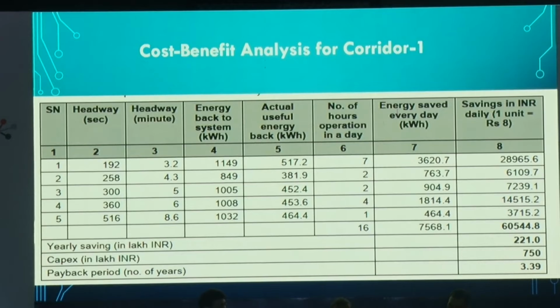We have done a cost benefit analysis for corridor 1 of Kanpur Metro. As per the headway in the DPR, considering 16 hours operation in a day, we could save an energy of around 7,500 units in a day, which translates into 2.2 crores rupees of saving in a year. Considering a cost of transformer 2.5 crores as of now, if we are putting 3 transformers in the corridor, the payback period is less than 3.5 years.